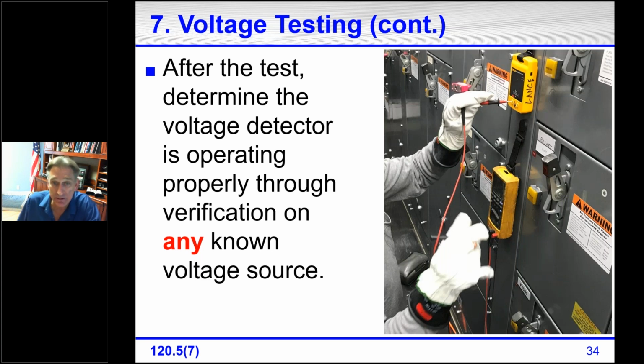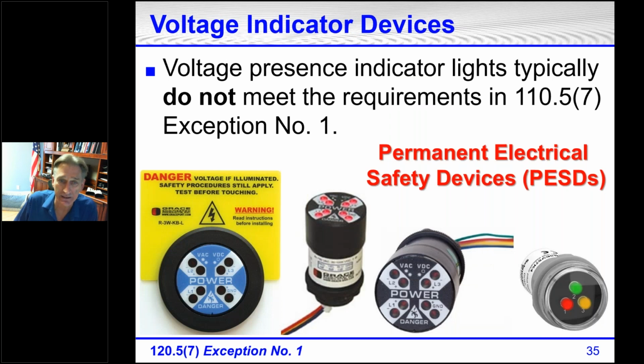This proving unit from Fluke is a great instrument. I don't have one with me, it's in the garage, but it is a great instrument to give you voltage at your source, at hand. It's got a nice magnet. You just put it right where you're working. Voltage presence indicator lights typically do not meet the requirement of 110.5(7), exception number 1. Exception number 1 is an absence of voltage tester.